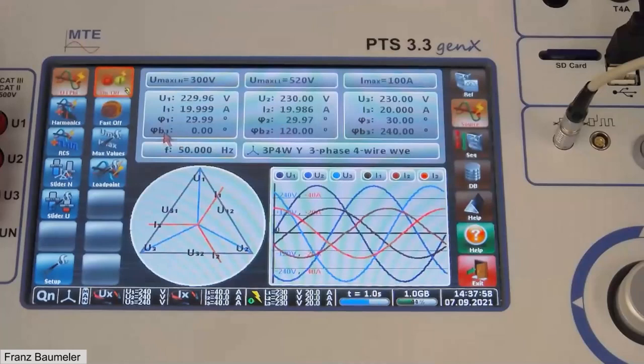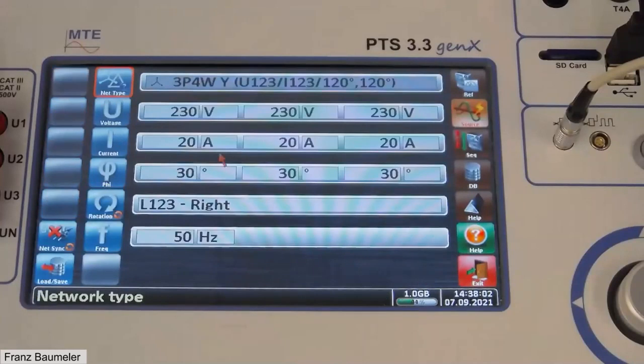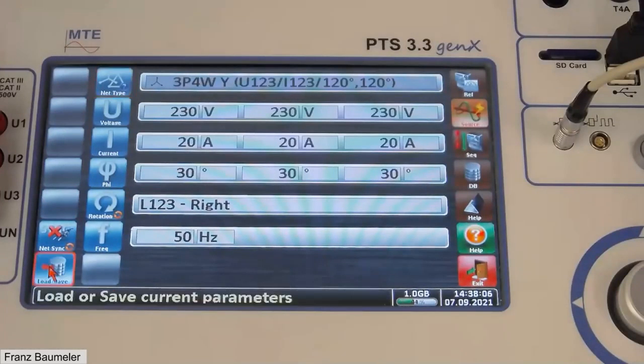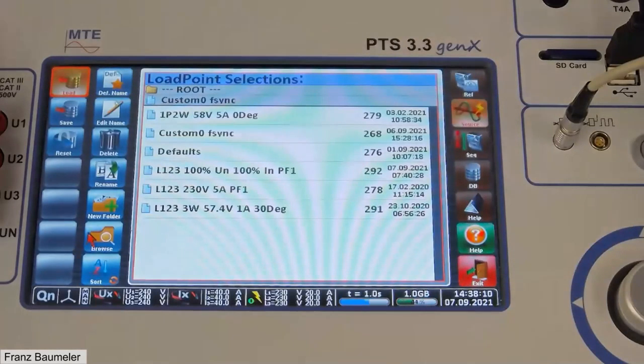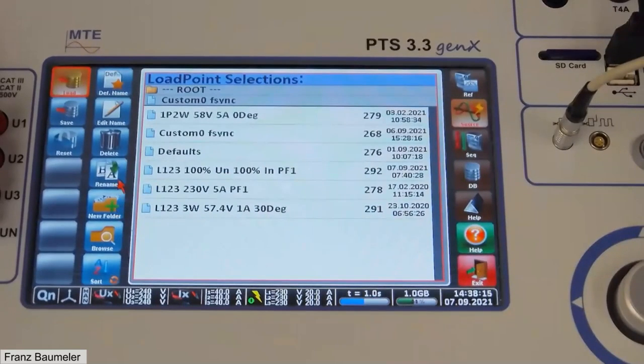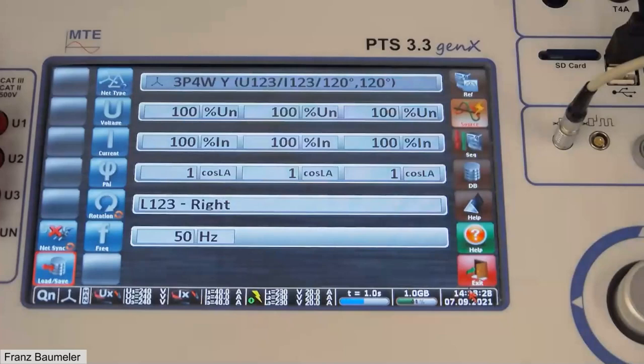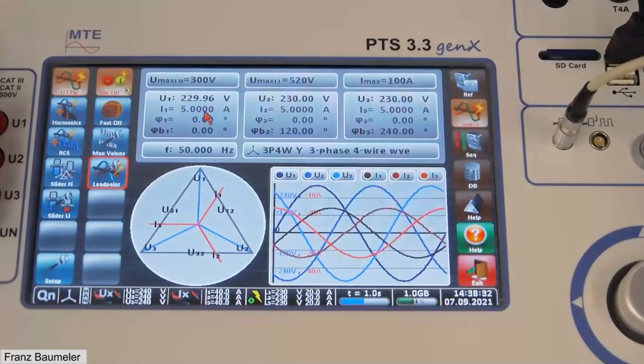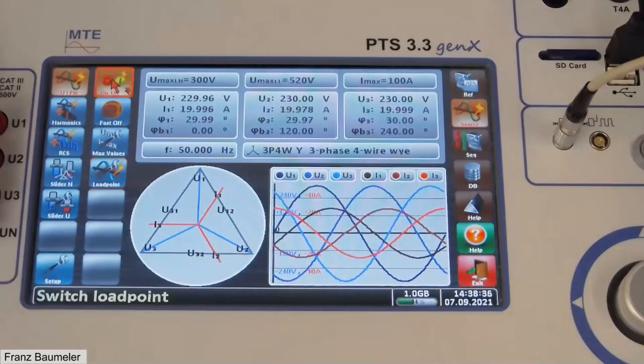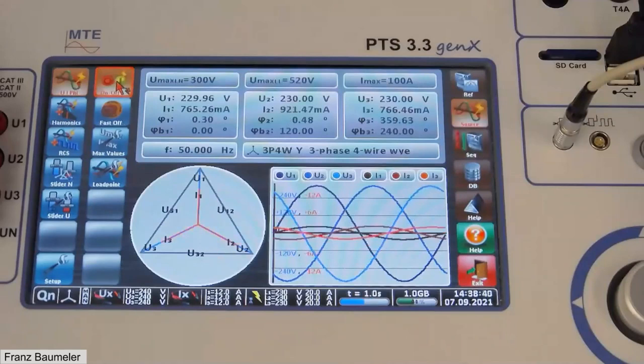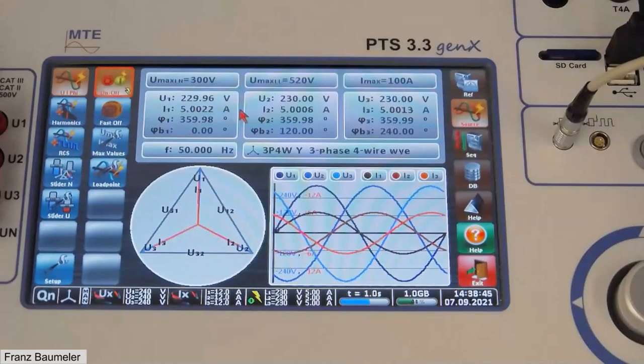On the source side, before I changed values manually, but you can do it more simply — you can load, save, and redefine settings. I had set values absolutely in voltage, current, and phase angle, but you can also do it relatively: percentage of nominal voltage, percentage of nominal current, and power factor. For example, I can load these settings — in our case 230 volt, 5 ampere, 0 degrees — and press start to apply the new settings. Now you can see it has switched on with 230 volts and 5 ampere. The possibility to save settings is very useful; we have a lot of positions where you can save settings.